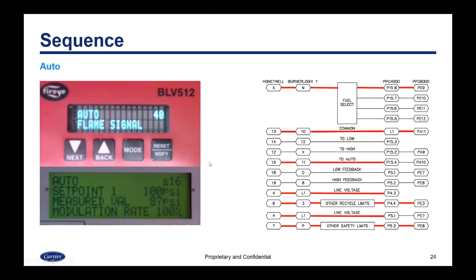Now that MTFI is over and we're going to transition to auto, we're going to switch the signal to auto from the flame safeguard to the PPC so that it knows it can modulate. There's no feedback in auto. Our limit string is still complete. Our safety limits are still complete. We still have power coming out from the blower output, obviously. So in auto, these are going to be the lines that have power.